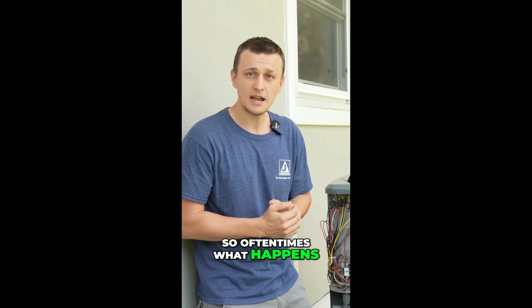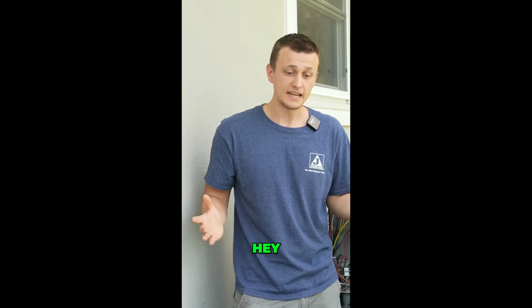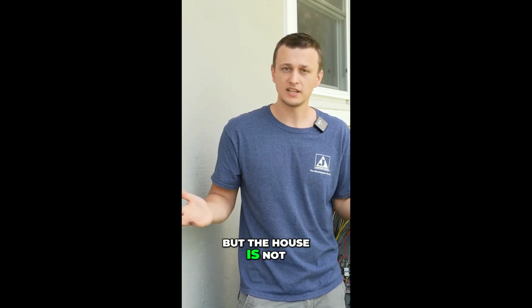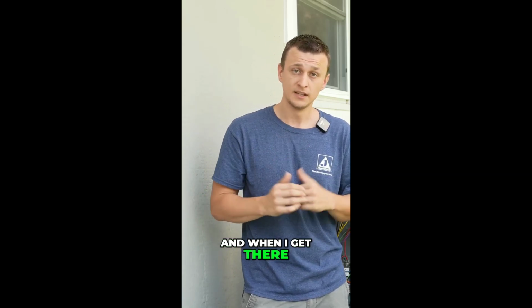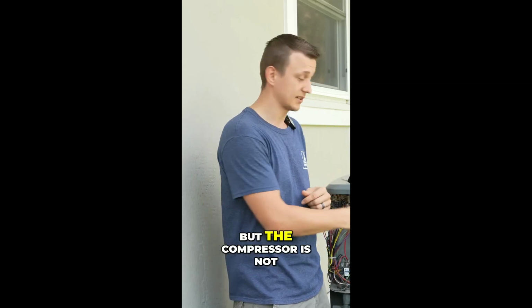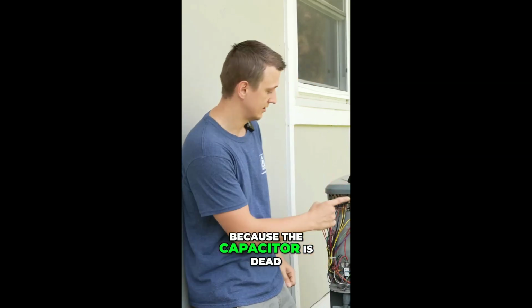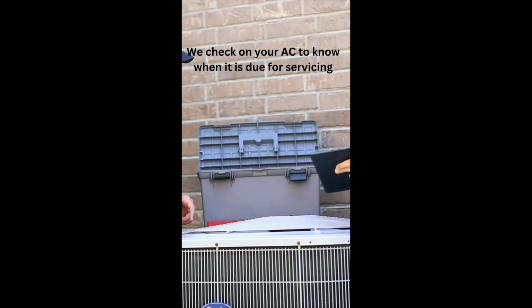So oftentimes what happens is a customer will tell me, hey, everything is working great, but the house is not getting cooled off. And when I get there, yeah, the two fans are working, but the compressor is not because the capacitor is dead.